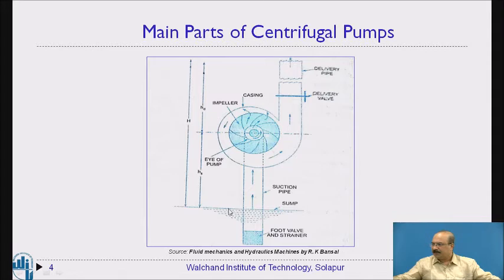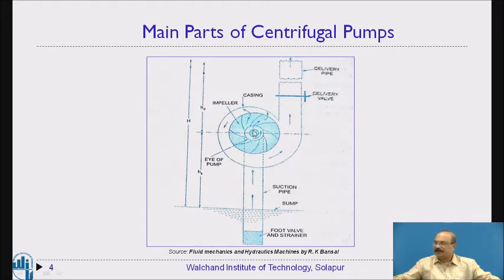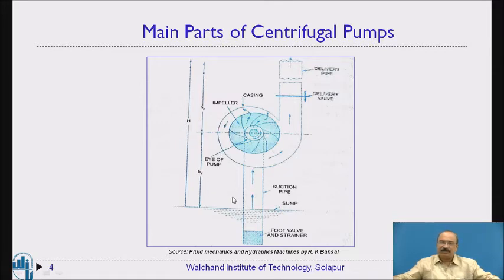Some important terms: from the water level in the sump up to the eye of the pump, this is called the suction head. From the eye up to the delivery point of the overhead tank, this is called the delivery head. The combination of these two is taken as the total head. These are the different heads we will study in the next section.